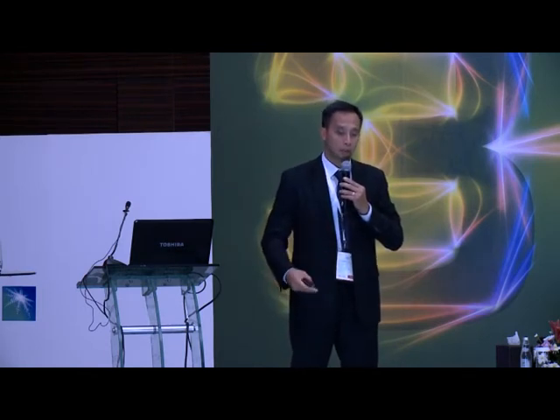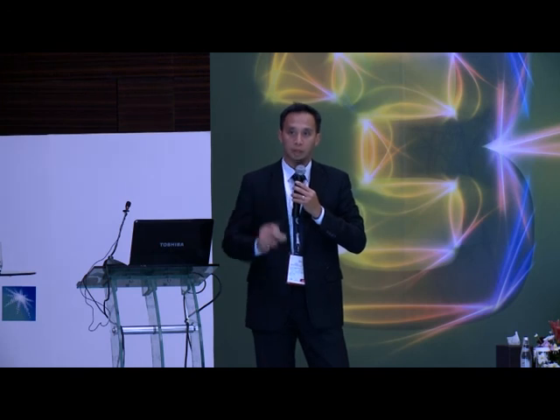And lastly, aging and/or obsolete equipment doesn't necessarily mean less safe. Like I said, we still have a lot of this equipment. It's still operating today. Our workers are maintaining this equipment, and everything is still online. So it's just the importance of doing proper PM. That's very relevant. We have to do proper PM on equipment in order to keep it running and within the tolerance bands of when we do our studies. We need those clearing time inputs to make sure they're within that range. And that's all.